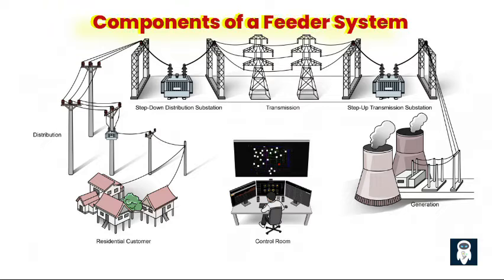Third, transformers play a crucial role in the feeder system. Distribution transformers at the substation or along the feeder step down the voltage to suitable levels for residential, commercial, or industrial loads. Fourth, protection devices — including fuses, circuit breakers, relays, and protective relays — are installed along the feeder system to detect and isolate faults. They monitor electrical parameters such as current, voltage, and power factor, and when a fault is detected, they trip the circuit to isolate the faulty section and protect the equipment.